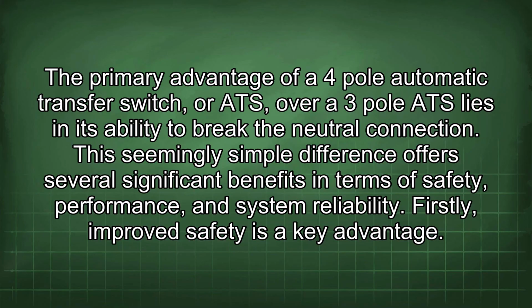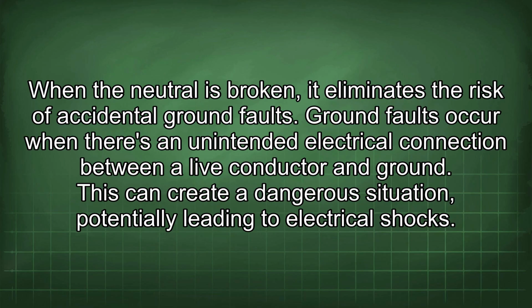The primary advantage of a 4-pole automatic transfer switch, or ATS, over a 3-pole ATS lies in its ability to break the neutral connection. This seemingly simple difference offers several significant benefits in terms of safety, performance, and system reliability. Firstly, improved safety is a key advantage. When the neutral is broken, it eliminates the risk of accidental ground faults.